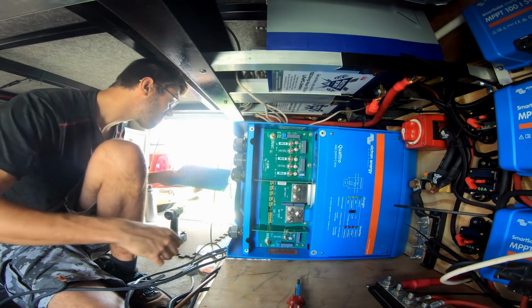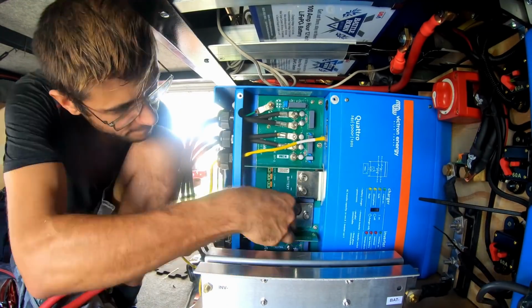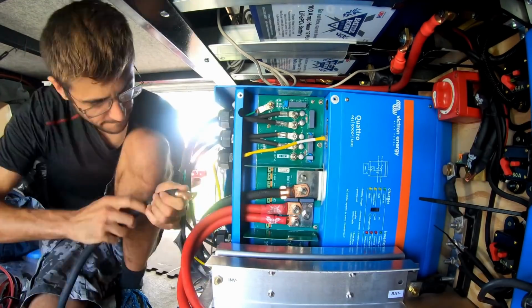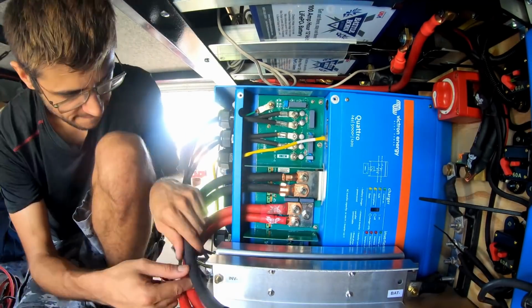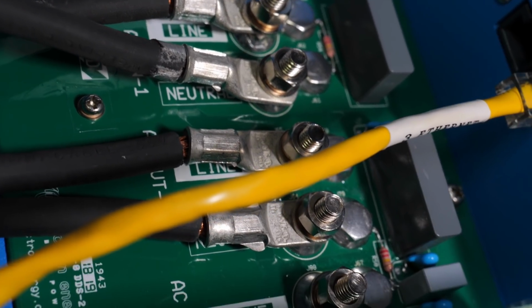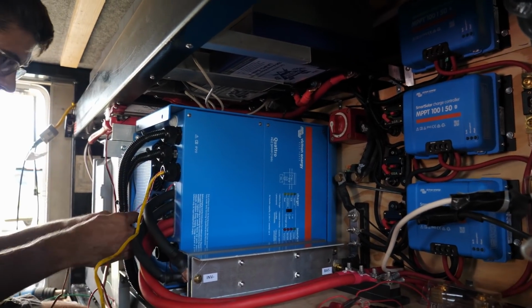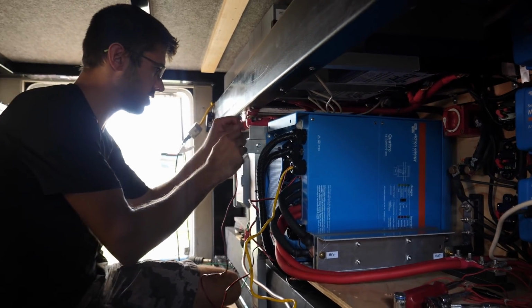The inverter hooks up to the positive and negative bus bars to pull power from the batteries and solar system. With the inverter hooked up to the batteries, the AC side needed to be wired to the transfer switch on both the input and output power leads.